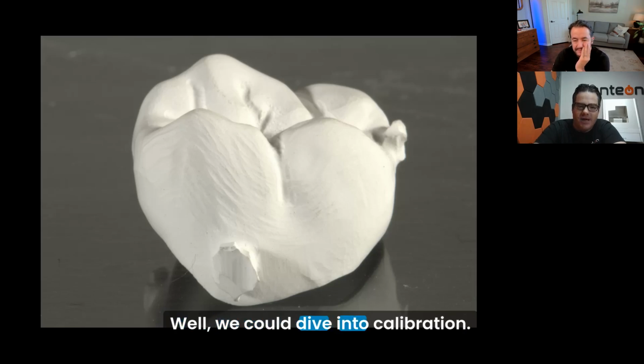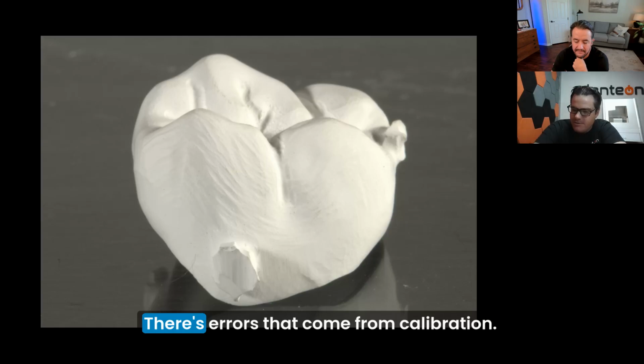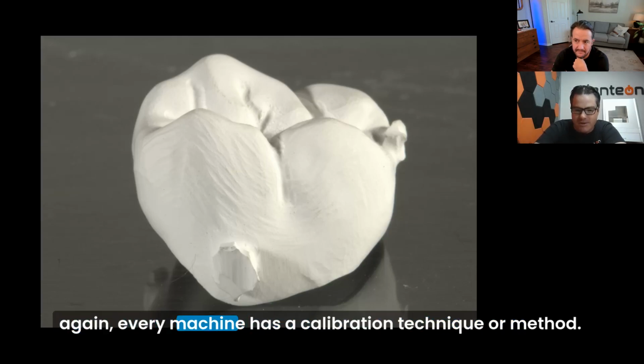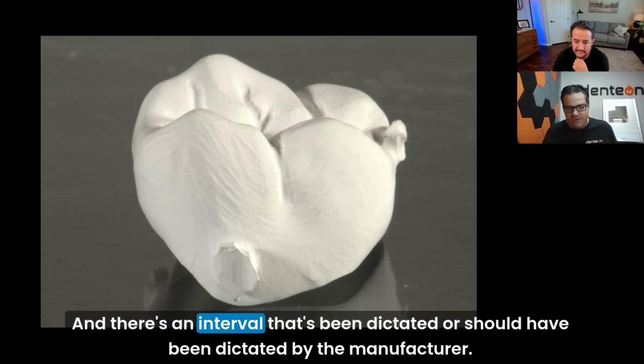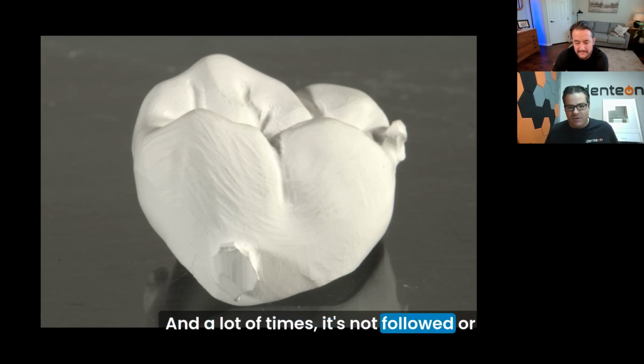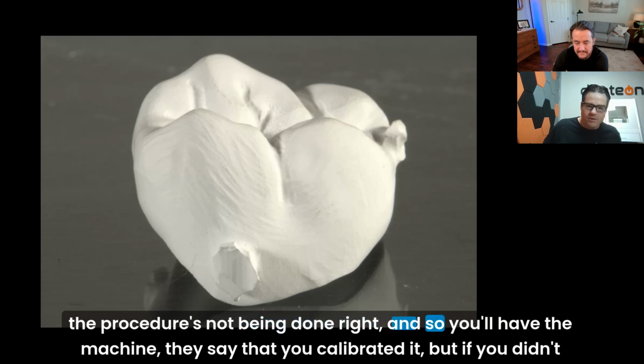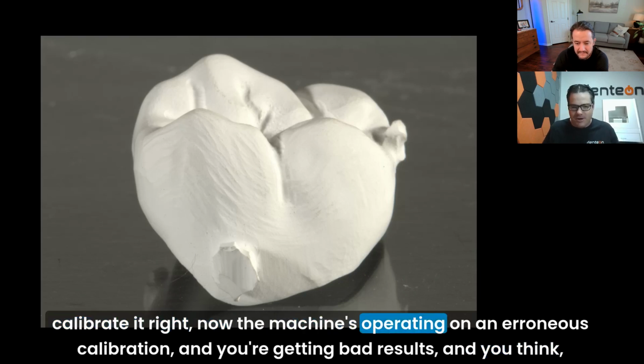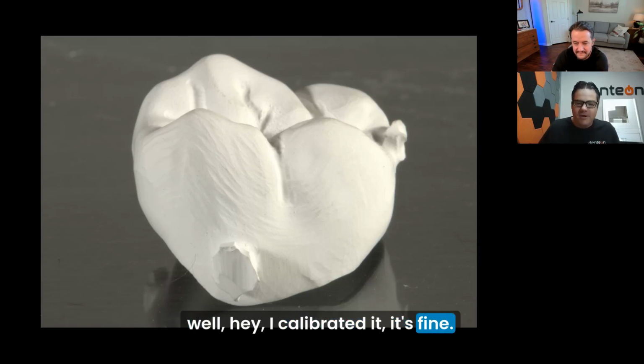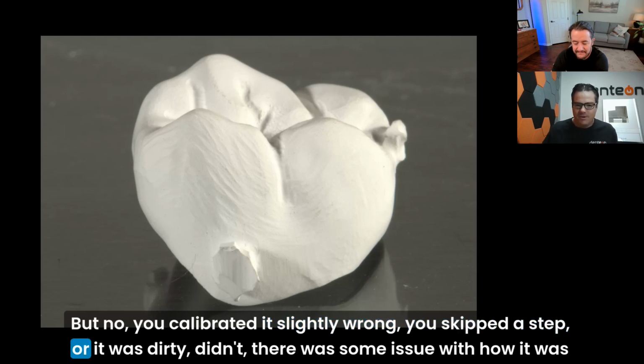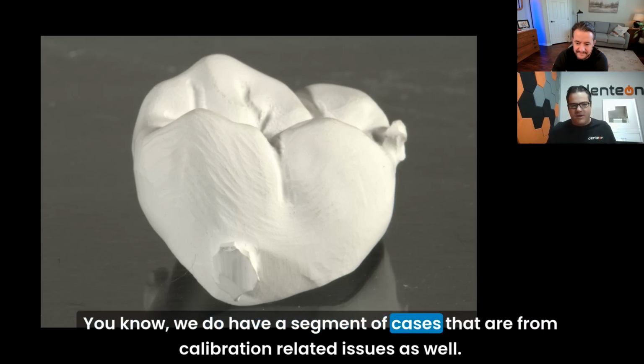Well, we could dive into calibration. There are errors that come from calibration. So every machine has a calibration technique or method, and there's an interval that's been dictated, or should have been dictated, by the manufacturer. And a lot of times it's not followed, or the procedure's not being done right. They say that you calibrated it, but if you didn't calibrate it right, now the machine's operating on an erroneous calibration, and you're getting bad results. And you think, well, hey, I calibrated it, it's fine. But no, you calibrated it slightly wrong. You skipped a step, or it was dirty, or there's some issue with how it was done. And so we do have a segment of cases that are from calibration related issues as well.